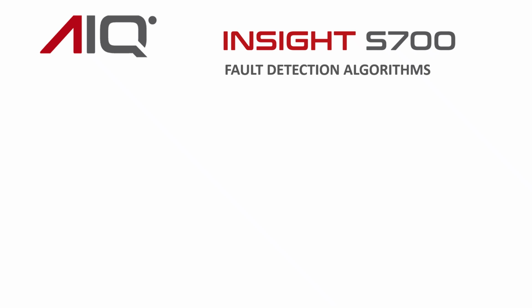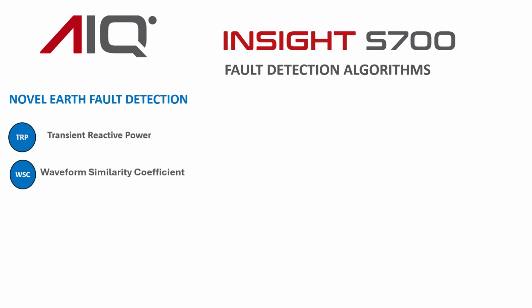So now we'll take a look at the fault detection algorithms. S700 has a range of traditional and novel fault detection algorithms for different applications and different neutral treatments. Novel earth fault detection algorithms consist of transient reactive power TRP and waveform similarity coefficient WSC.